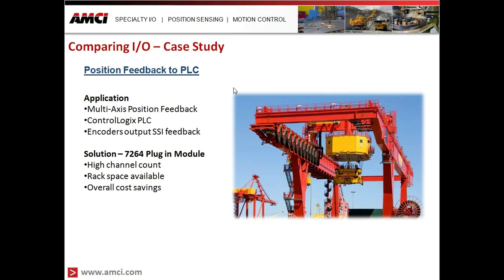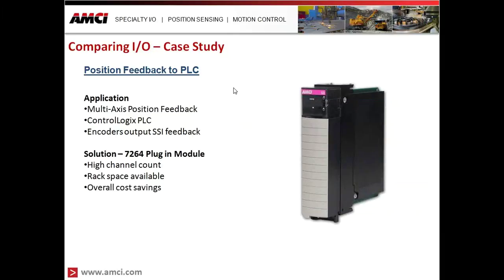The first case study is a position feedback application. A gantry has both X and Y axes along with a Z axis to monitor — four sensors total feeding back to a ControlLogix PLC. The encoders output SSI feedback. An SSI interface module that plugs directly into the ControlLogix was selected because it provides a high channel count, interfacing all four sensors into one plug-in card. With rack space available and the high-density module, it provides overall cost savings compared to using four individual SSI interfaces on a distributed point IO solution.